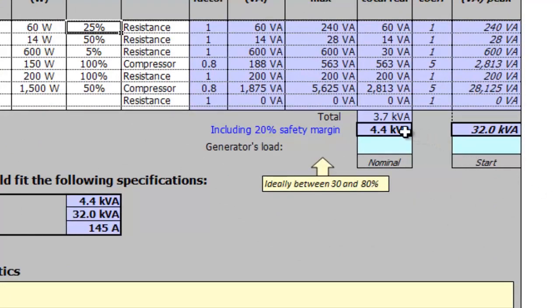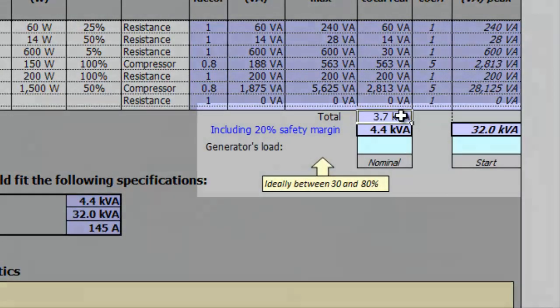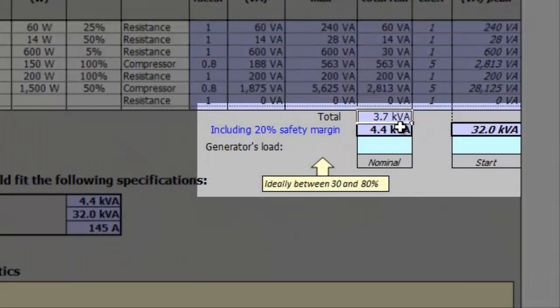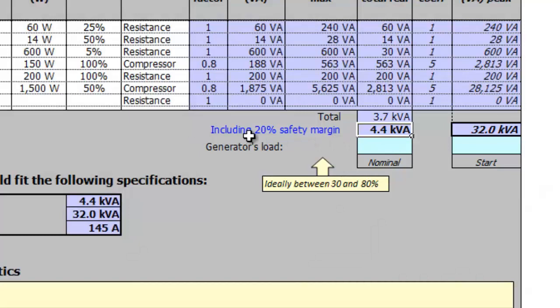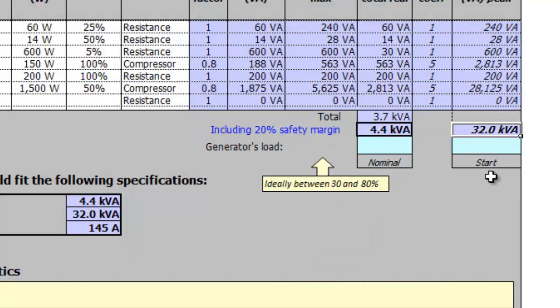Now we can see the estimate of the total power consumption of the electrical installation to be supplied by the generator. The total with a 20% safety margin and the peak current if all the appliances were plugged in at the same time.